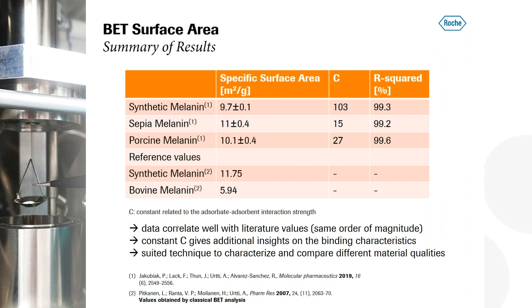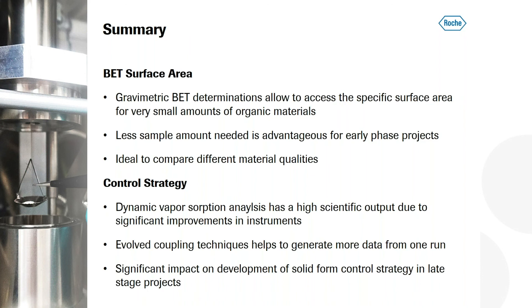With that, I want to conclude. I think I showed you that with this gravimetric BET determinations using the DVS, it allows you to detect the specific surface area for very small amounts of organic materials. I also want to highlight that you analyze your sample in the ambient conditions, which means that you don't have a clean surface by vacuum or something like that. So it's really your sample. You just put in your system. You need less sample amount, which is very advantageous for early phase projects where you don't have so much material. And it's really ideal to compare different material qualities if you run a series and can compare your DVS data with each other.